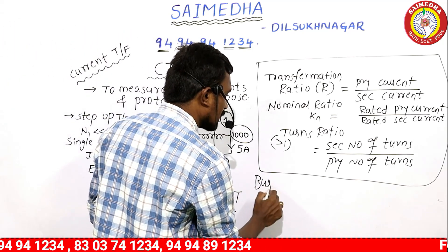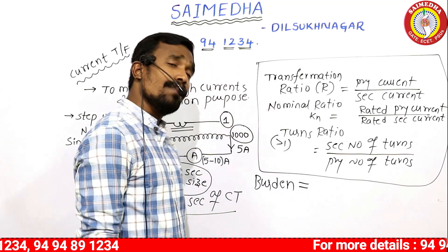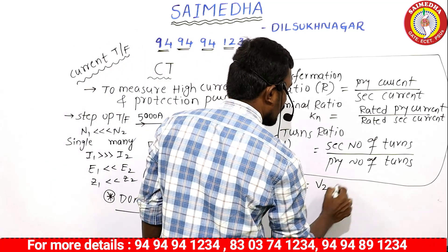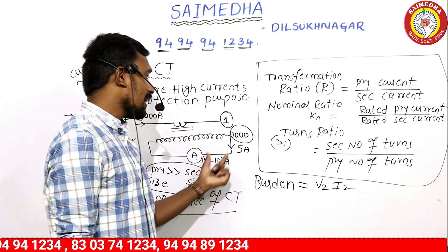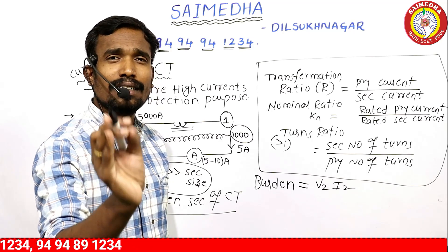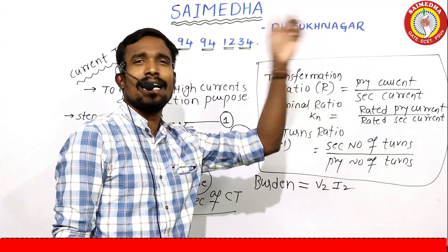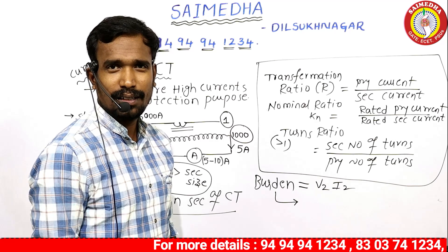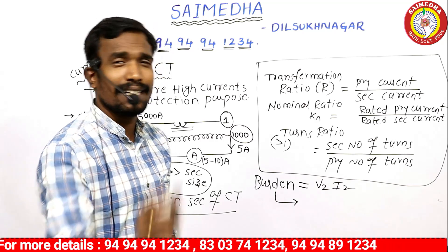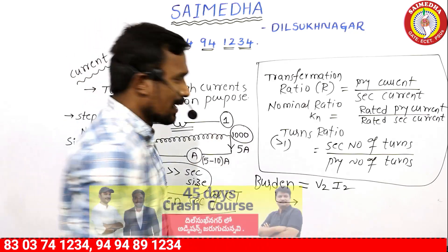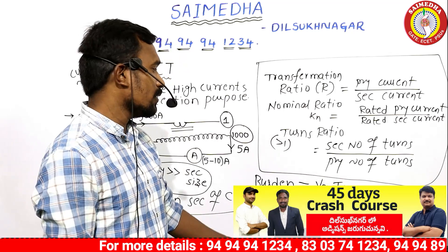Next is the burden on the transformer. The burden on an instrument transformer equals secondary voltage multiplied by secondary current. This applies to both CT and PT. The units of burden are volt-amperes — not kilowatts, not megawatts, not kVA — just volt-amperes.